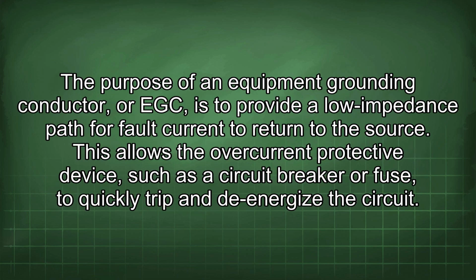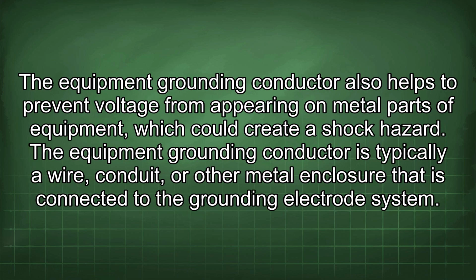The purpose of an equipment grounding conductor, or EGC, is to provide a low impedance path for fault current to return to the source. This allows the overcurrent protective device, such as a circuit breaker or fuse, to quickly trip and de-energize the circuit. The equipment grounding conductor also helps to prevent voltage from appearing on metal parts of equipment, which could create a shock hazard.